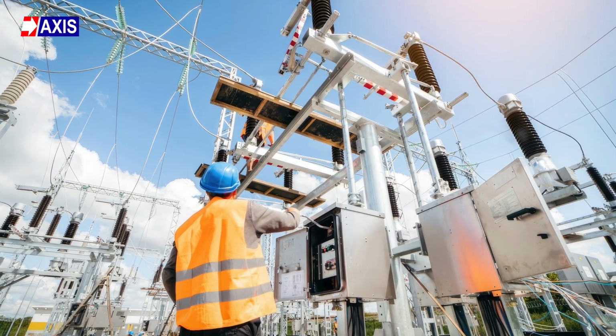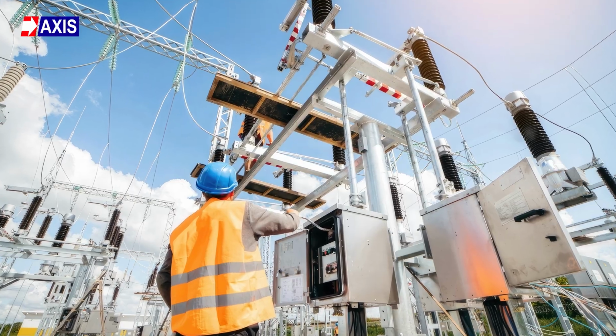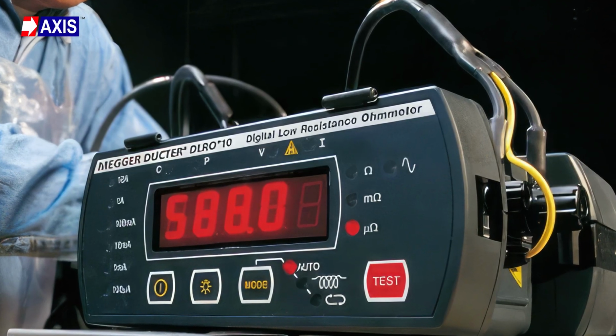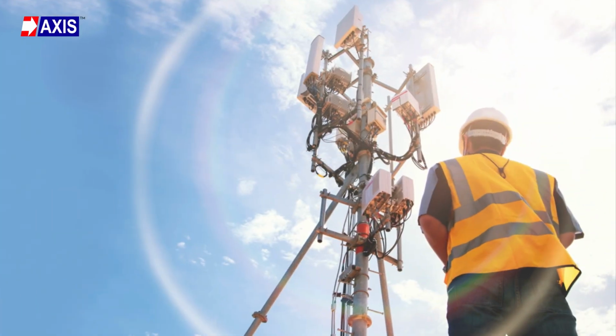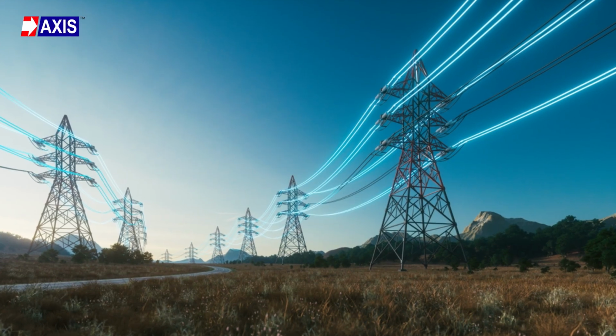The added minerals improve conductivity, while the moisture-retaining agents help keep water around the electrode even in dry conditions. This prevents air gaps and ensures stable contact with the surrounding soil. Axifill is used in substations and high-voltage yards where consistent low resistance is essential for handling fault currents. It also works well in places like telecom networks and transmission and distribution towers.